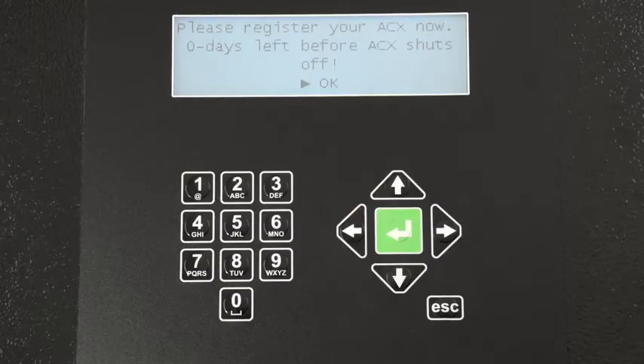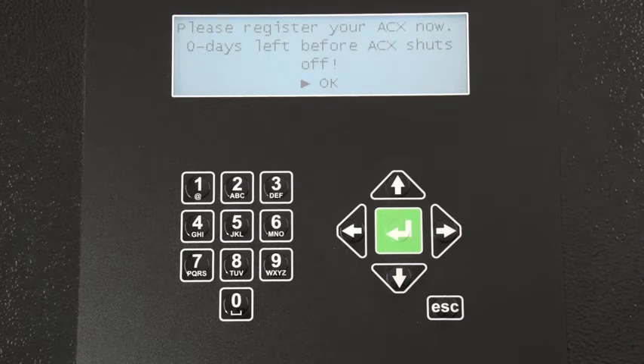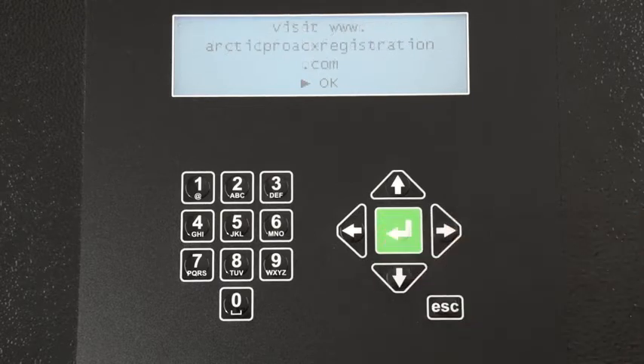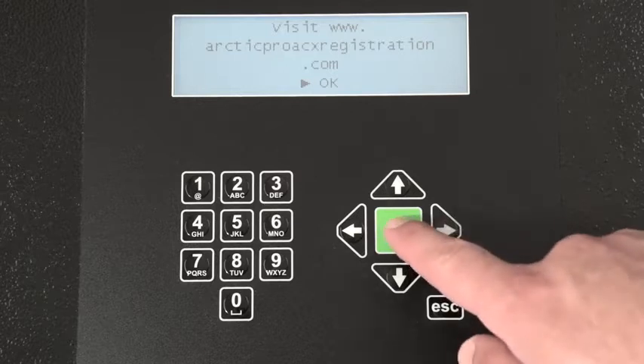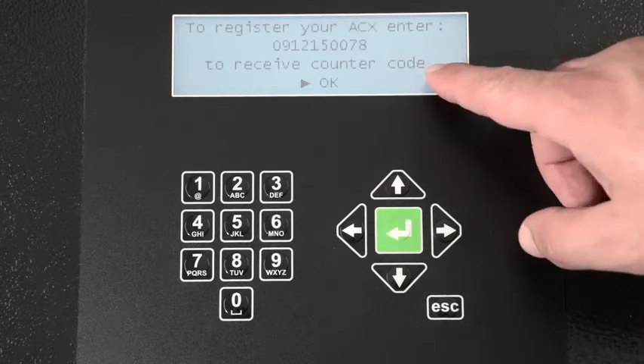The ACX1120 and 1150s must be registered within 30 days once they're first turned on. This machine, you can see on the screen, has hit 0 days. It will not let us go any farther until we register it at this point. So we're going to hit OK. It gives us the registration website. Hit OK. And what we'll do now is we'll go to that website and we will enter this number along with the shop information, and then it will give us the counter code.